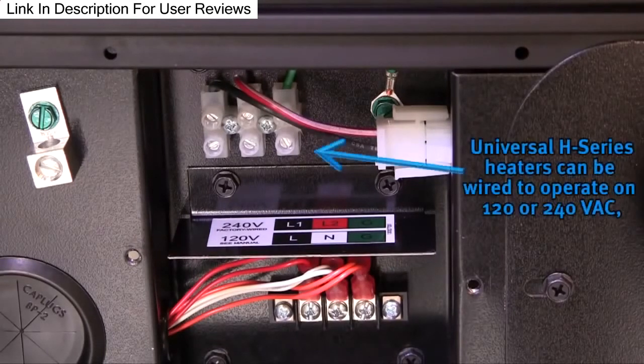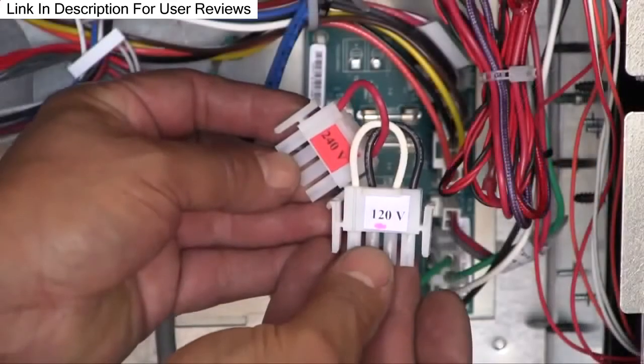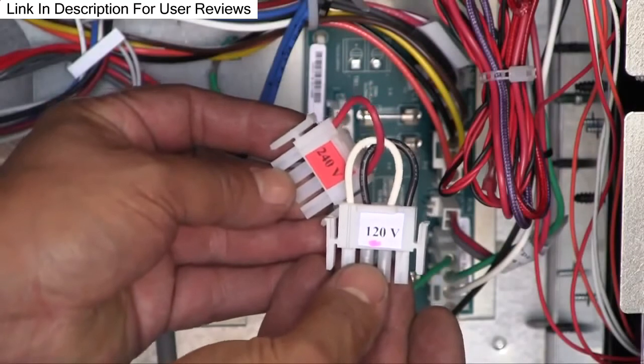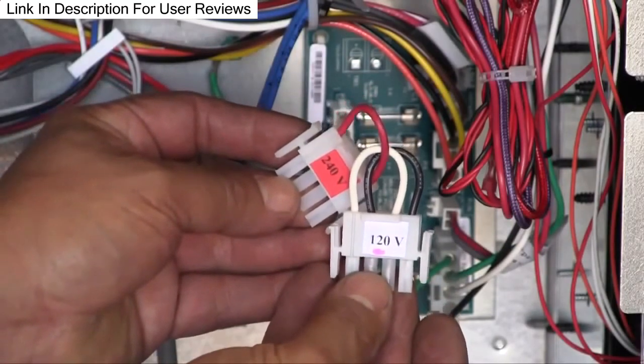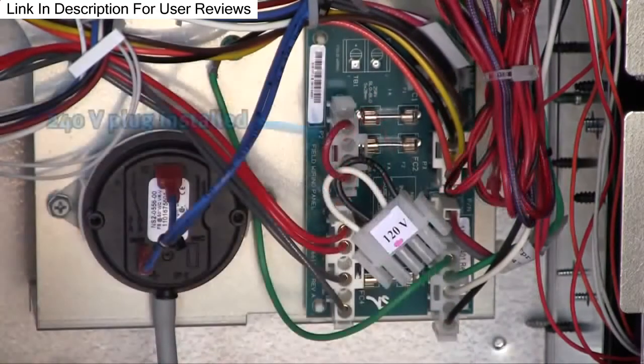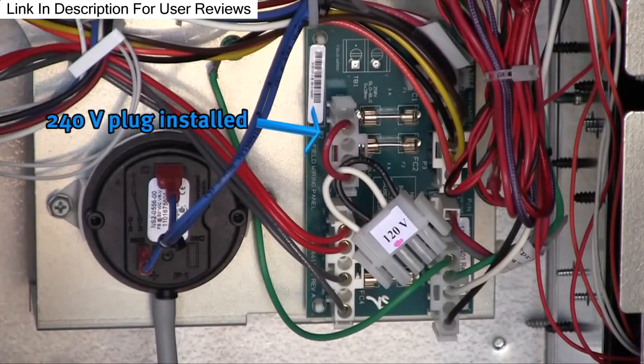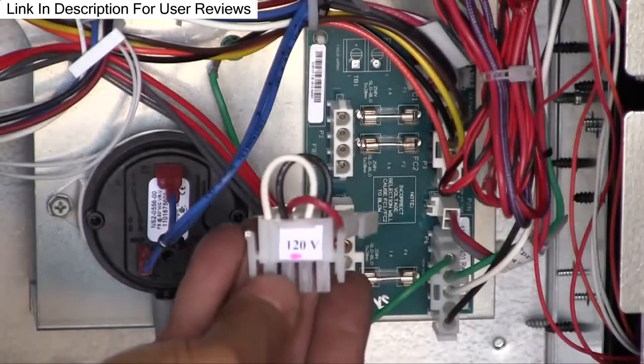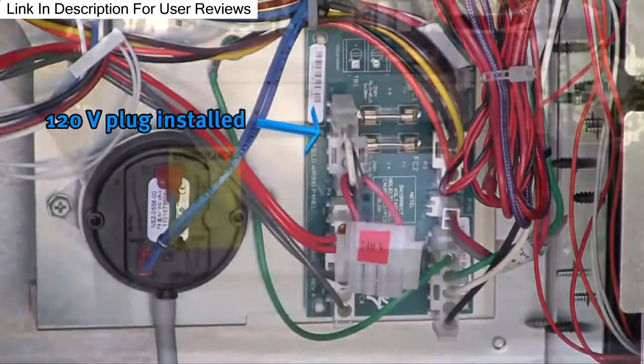They can be wired for either 120 or 240 volts AC. The heater is equipped with a pair of voltage selector plugs, which are accessed by removing the front door of the heater. The heater ships with a 240 volt plug installed on the fused circuit board located in the electrical compartment behind the control board. If the heater is connected to 120 volts, the 120 volt plug must be installed.